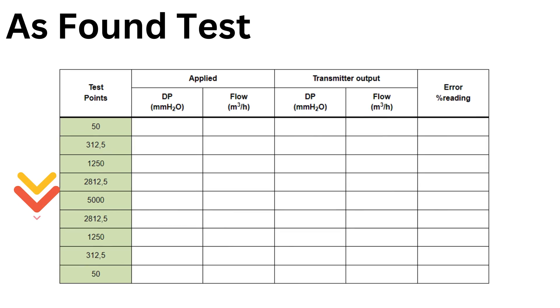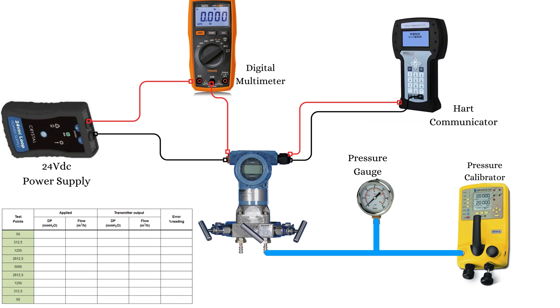Start the validation procedure with zero pressure on the pressure calibrator and increase the pressure until you reach the pressure value of the first test point. Note down the reading from the pressure calibrator in the second column, applied DP, and the reading from the transmitter in the fifth column, transmitter output flow. Similarly, apply the pressures of the other test points in the order they appear in the table. Note down the readings from the pressure calibrator and the transmitter in the appropriate columns.